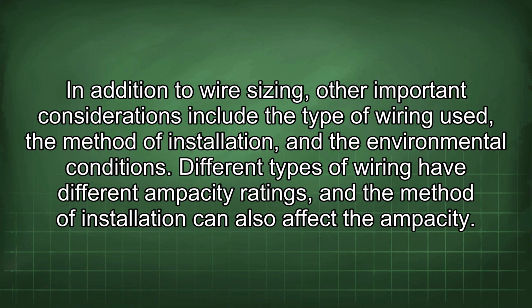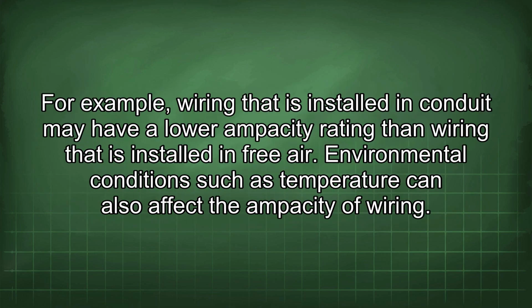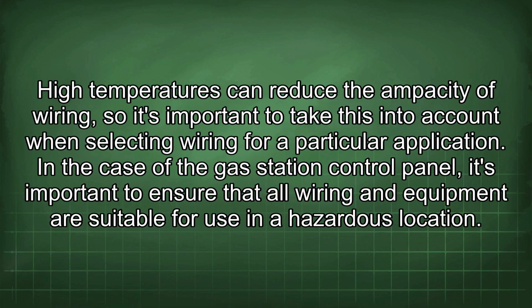and the environmental conditions. Different types of wiring have different ampacity ratings, and the method of installation can also affect the ampacity. For example, wiring that is installed in conduit may have a lower ampacity rating than wiring that is installed in free air. Environmental conditions such as temperature can also affect the ampacity of wiring.